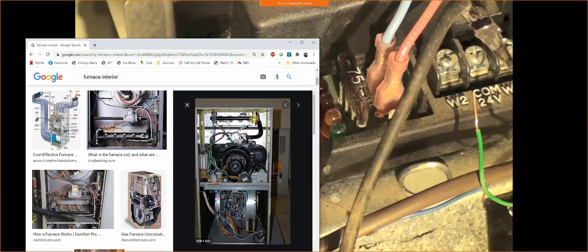hot surface igniter. If I have a blockage in my piping, let's just say there's water, there's a bird, somebody threw rocks in there, whatever the case may be, well, the piping isn't going to be clear, and my pressure will never increase. And if my pressure never increases, well, guess what? My furnace won't light. So when you go onto a site, we need to make sure that everything is operating like it's supposed to.